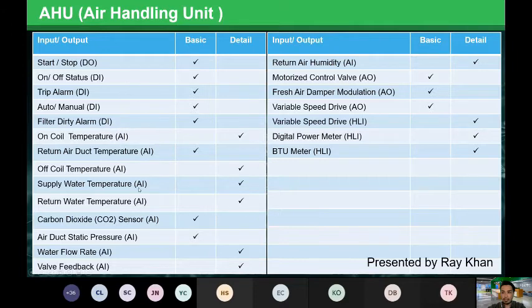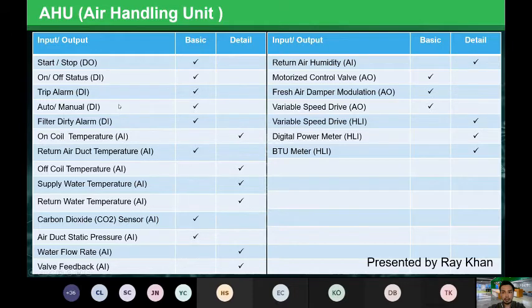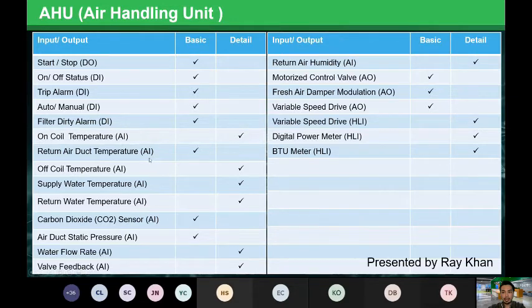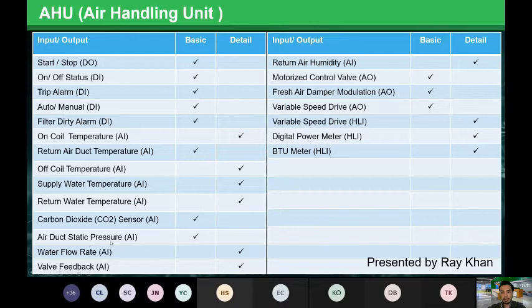Let me go through the different points allocated for AHU. First, we have start/stop using digital output. Then digital inputs for: on/off status of the AHU, trip alarm status, manual or auto selector status, and filter dirty alarm status. For analog inputs we have: on-coil temperature, return air duct temperature, off-coil temperature, supply water temperature, return water temperature, carbon dioxide level, air duct static pressure, water flow rate, and valve feedback — all analog values.